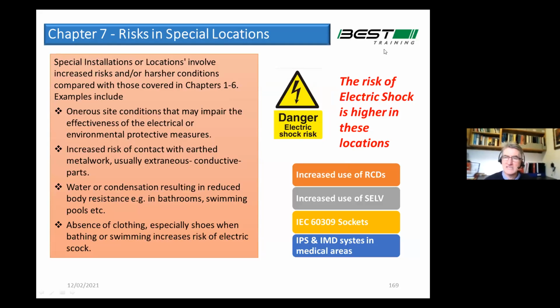Risks, special locations. Chapter 7 deals with special locations or installations. The reason they're in here is because there's a higher risk of electric shock or a higher risk of loss of life. For example, in a hospital, an interruption of the power could cause someone to die, like someone on life support. So in most cases, the risks are dealt with by increased use of RCDs and increased use of SELV. You'll find there are lots of references in, for example, marinas, campsites, industrial locations, etc., to IEC 60309 sockets, or commando sockets, as we call them in the industry.